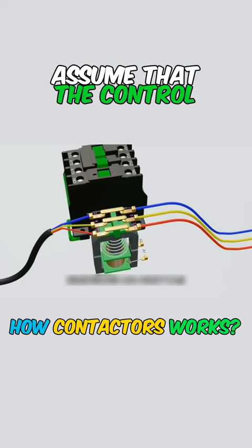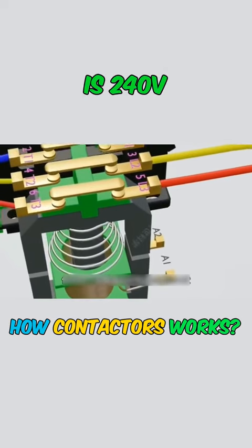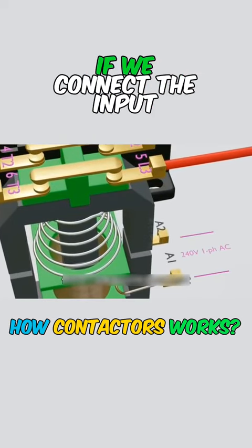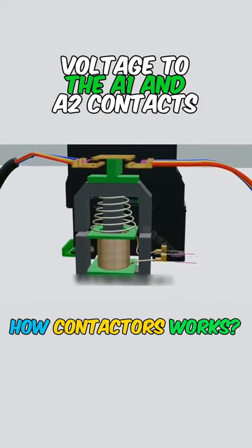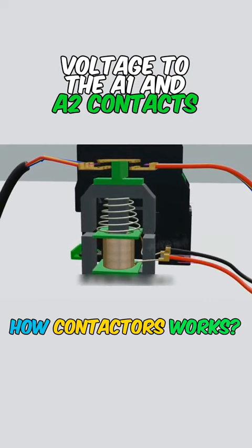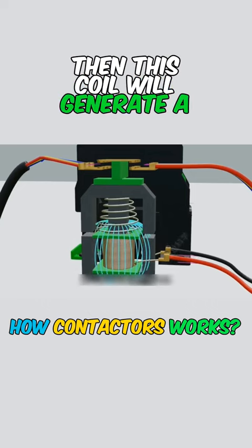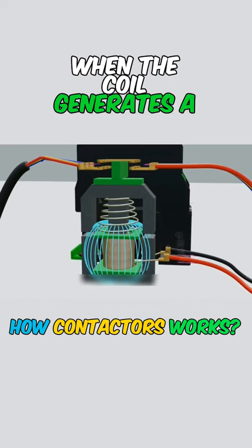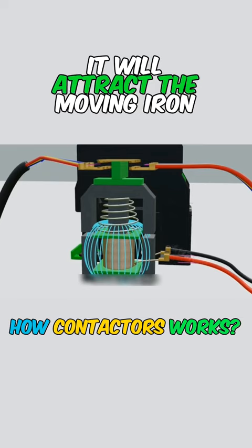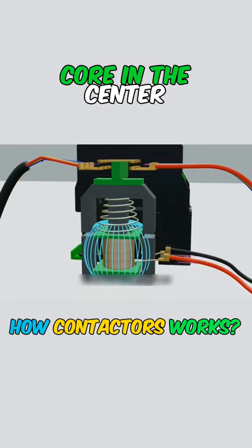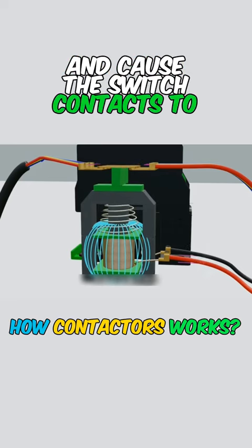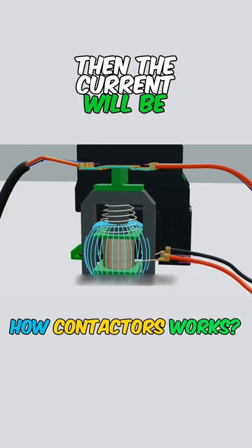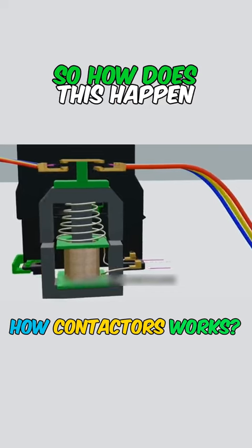Assume that the control voltage of this contactor is 240 V. In other words, if we connect the input voltage to the A1 and A2 contacts, then this coil will generate a magnetic field. When the coil generates a magnetic field, it will attract the moving iron core in the center and cause the switch contacts to close. Then the current will be transmitted to the load device. So how does this happen?